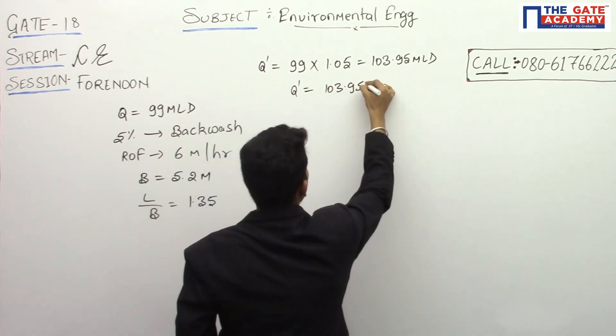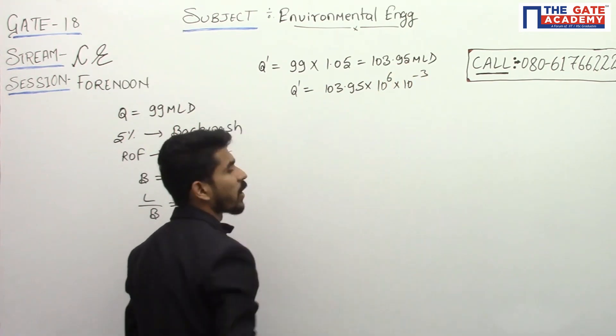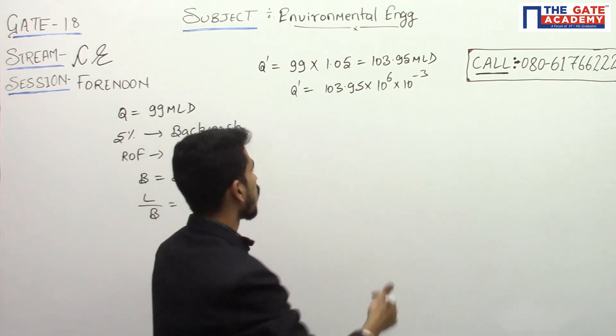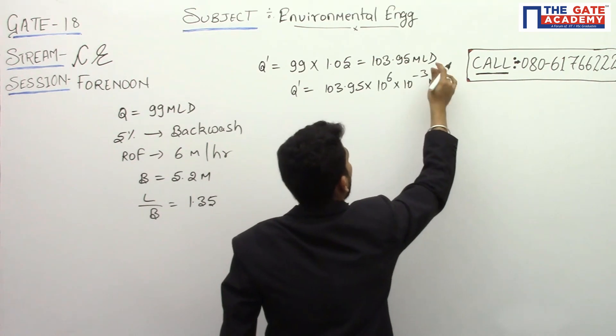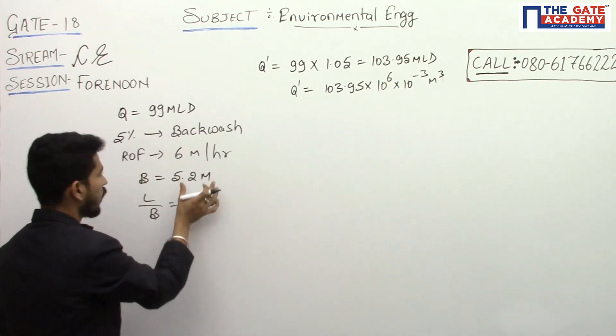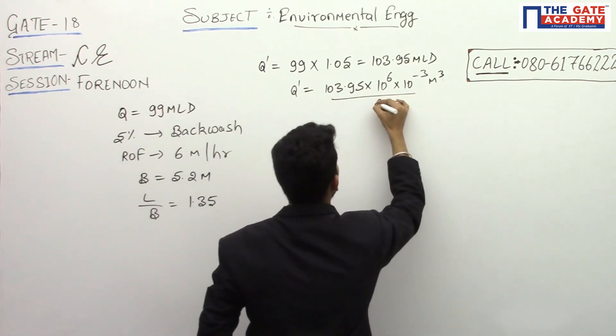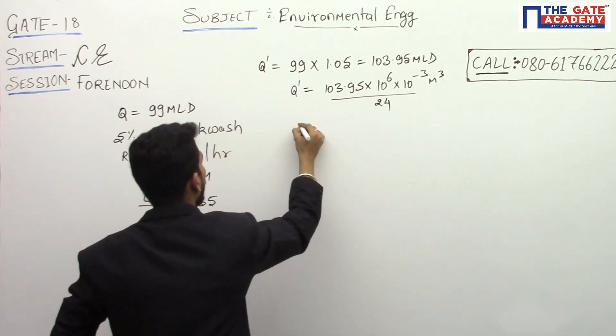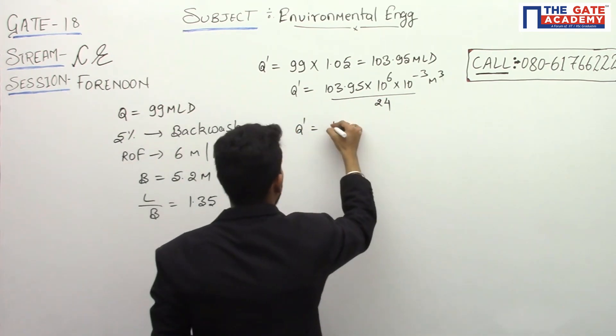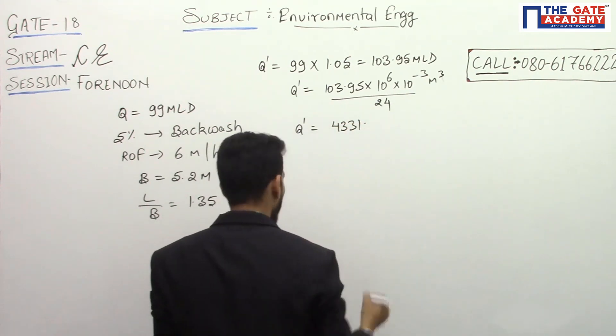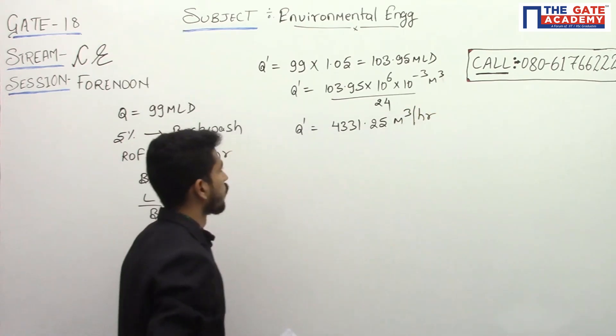Let us convert 103.95 MLD into cubic meters: multiply by 10 to the power 6 liters, then by 10 to the power minus 3 to get cubic meters. Then divide by 24 to convert per day to per hour, because the rate of filtration is given in per hour. So the effective discharge Q equals 4331.25 cubic meters per hour.